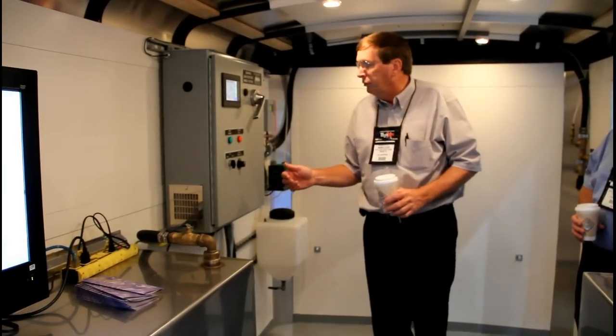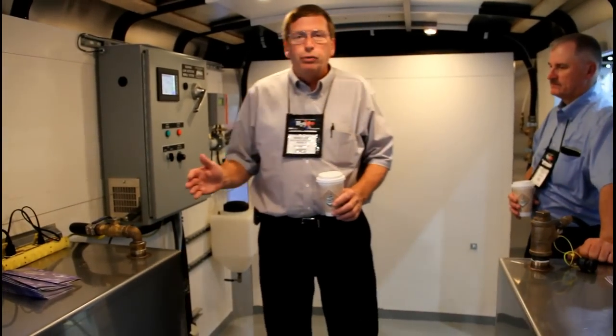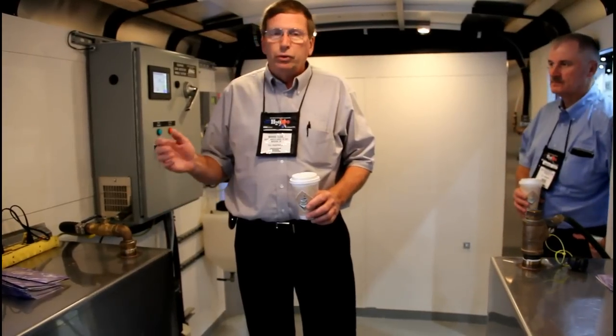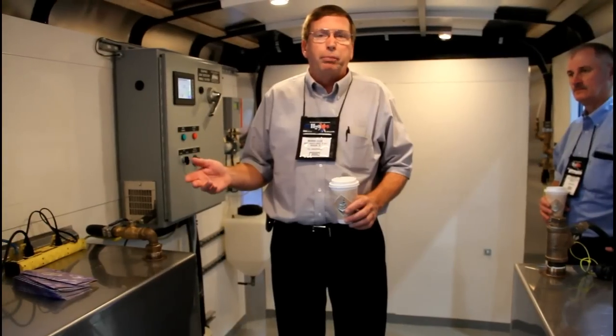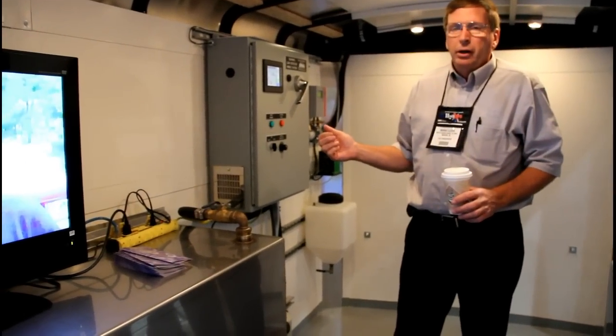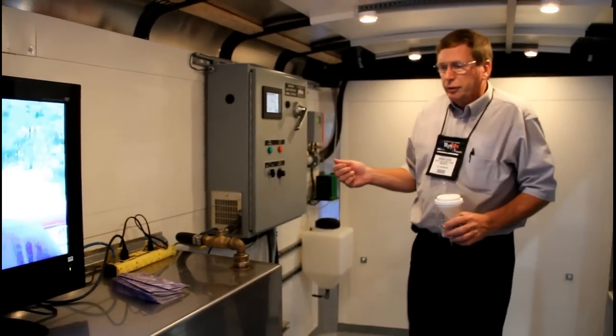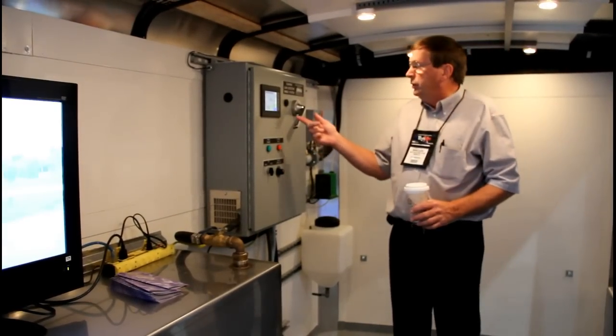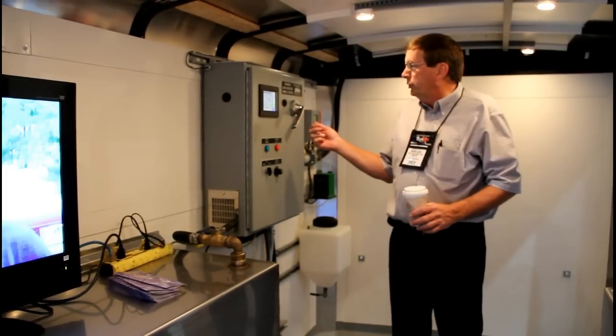What I do normally when I get to a system and I hook up to a fire hydrant when I'm doing leak detection is when I get my tanks about half full, I'll do a chlorine residual, and if I'm somewhere around 1.5 parts per million, since I have the ability to chlorinate, I will raise that level to about 1.9 leaving the trailer.